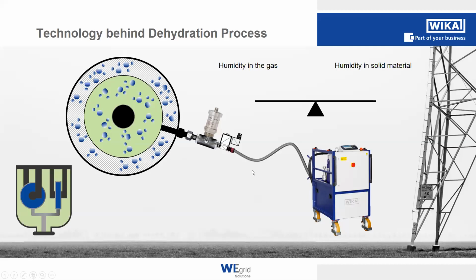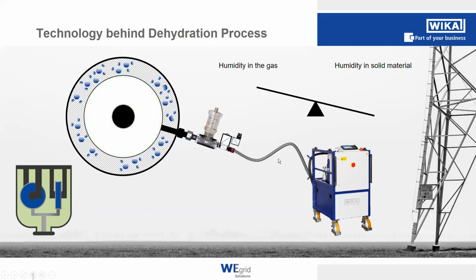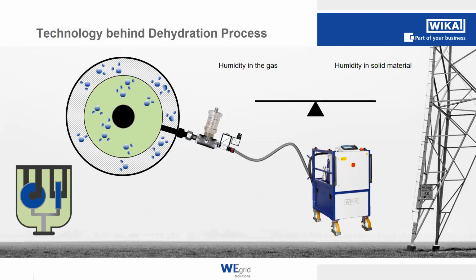So when we start the process, we are sucking out a bit of gas into our GAD, running it in a circle through our filters and drying the SF6 gas. After this is done, we are pumping the dried gas back into the compartment and give the compartment a specific time to equalize itself again. In this equalization phase, we get the water from the compartment wall back into the now drier gas. Like I said before, the humidity always tries to get into a counterbalanced state.